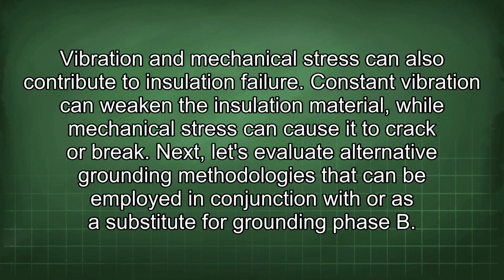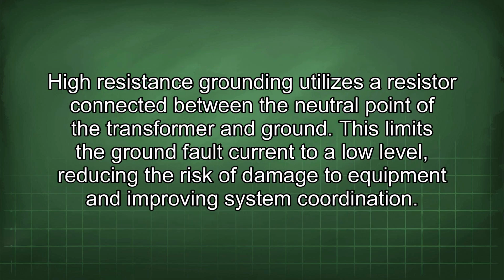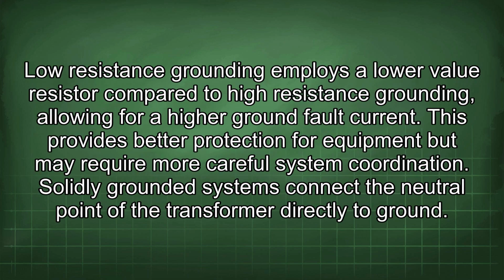Next, let's evaluate alternative grounding methodologies that can be employed in conjunction with or as a substitute for grounding phase B. High resistance grounding utilizes a resistor connected between the neutral point of the transformer and ground. This limits the ground fault current to a low level, reducing the risk of damage to equipment and improving system coordination. Low resistance grounding employs a lower value resistor compared to high resistance grounding, allowing for a high ground fault current. This provides better protection for equipment but may require more careful system coordination.